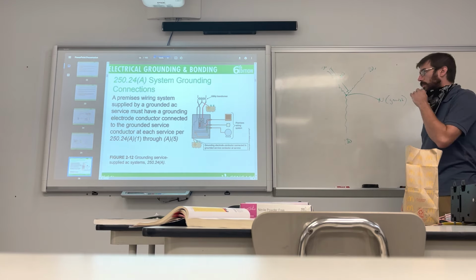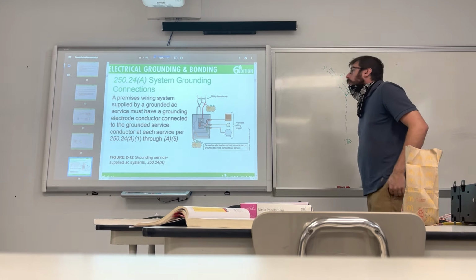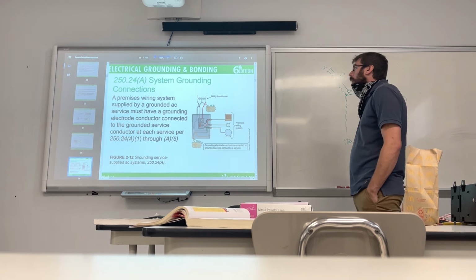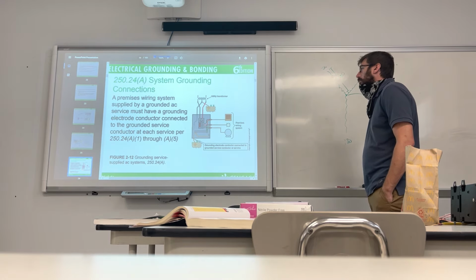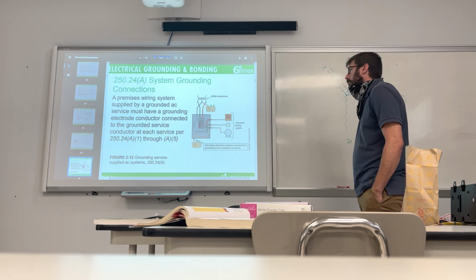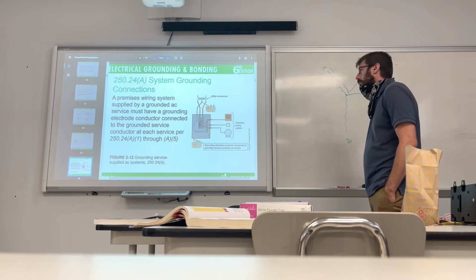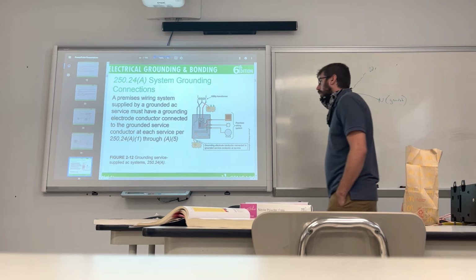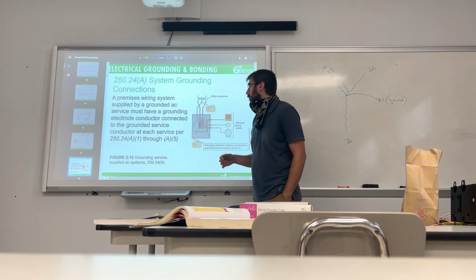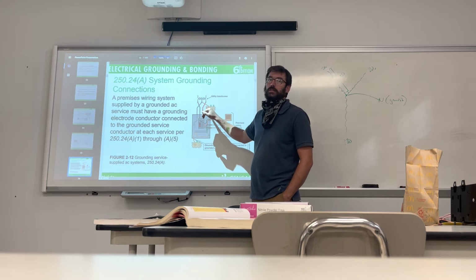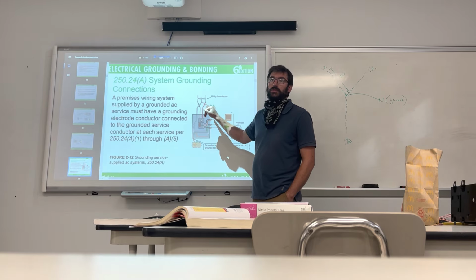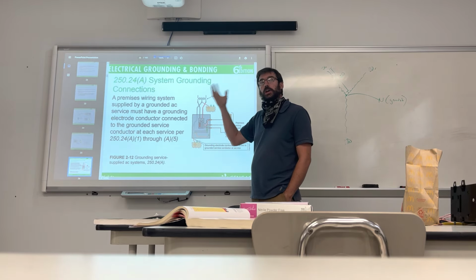System grounding connections. A premises wiring system supplied by a grounded AC service must have a grounding electrode conductor connected to the grounded service conductor at each service per 250.24(A)(1). And now what I mentioned before, the utility transformer, there it is. There's that ground, that sneaky ground that nobody was talking about, nobody was thinking about. Now you can at least know.